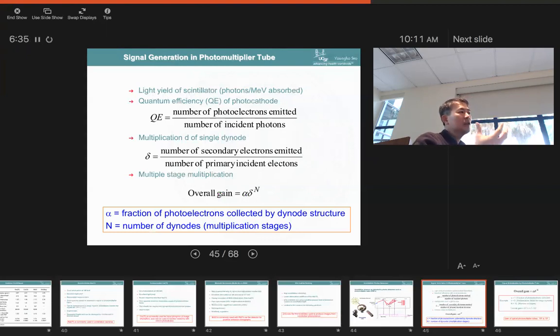When we talk about some scintillator being brighter and some not being brighter, the brightness is the light yield. So two of the most common examples to compare are sodium iodide, which produces about 38,000 photons per 1 mega electron volt of energy, and a less bright scintillator material, BGO. BGO is a lot less bright.